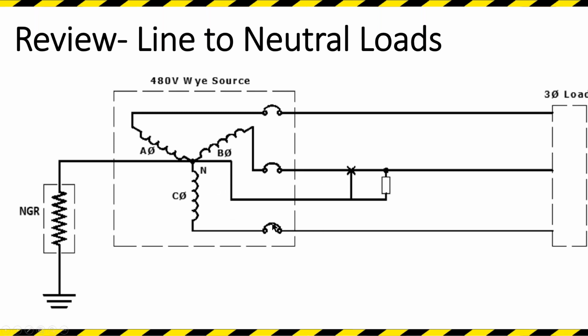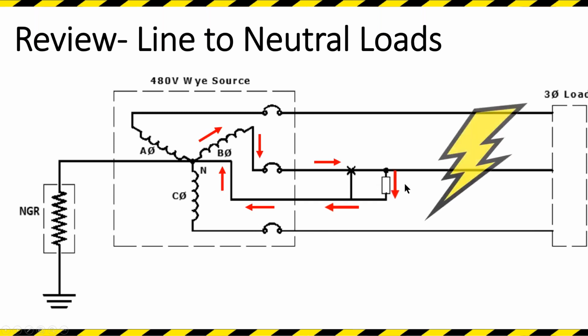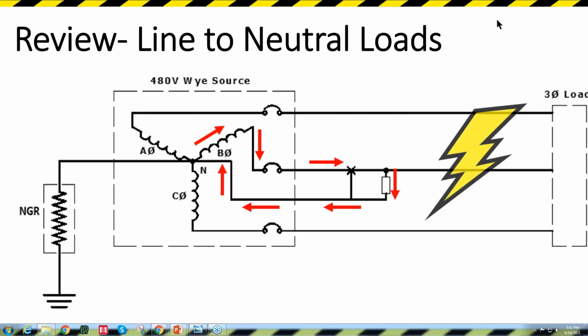So we have a line-neutral load here. It's not permitted by the NEC. Why is that? Essentially, you could bypass the resistor. We're looking at a short, bypassing the resistor. The whole idea of the resistance ground system is to make sure the resistor is basically your only intentional ground fault path. You're making sure the current gets choked off, or impeded, so a smaller current flows through here. If you're bypassing that resistor, you're going to have a greater amount of current. You're also potentially going to have no indication, so you could be in a dangerous situation for your personnel. That's why the NEC says no. It's a big no on that one. Typically, I don't need to go into this in detail, but usually you would have isolation transformers if you want to have line-neutral loads. That's how you would get by this issue.